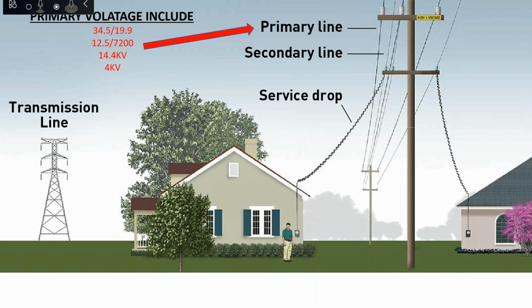You have 14.4, which is another primary voltage, mainly out in some of our rural areas. But our main two voltages that we run for our primary distribution system are 12.5, which is 7,200 volts phase to ground, 12,500 volts phase to phase, and then 34.5, which is 19,900 volts phase to ground or 34,500 volts phase to phase. Those are generally the two that we use.